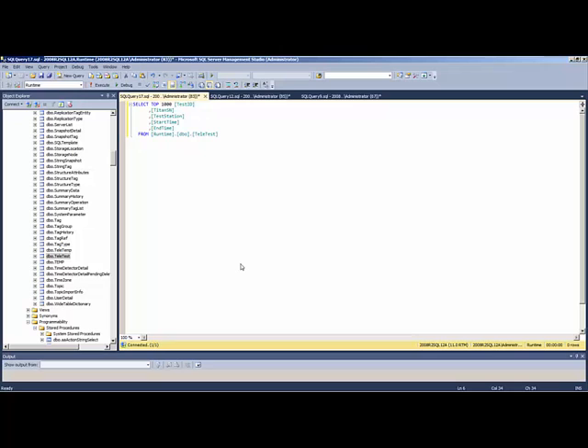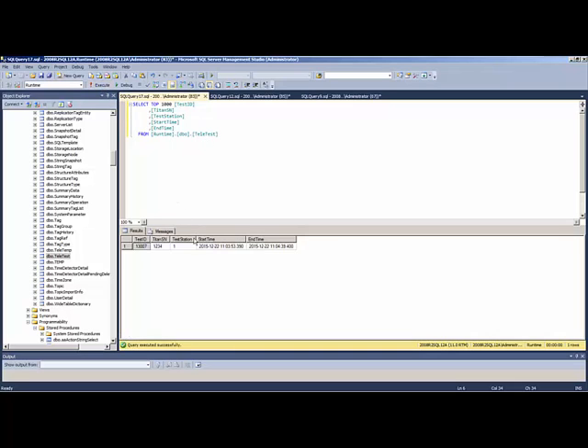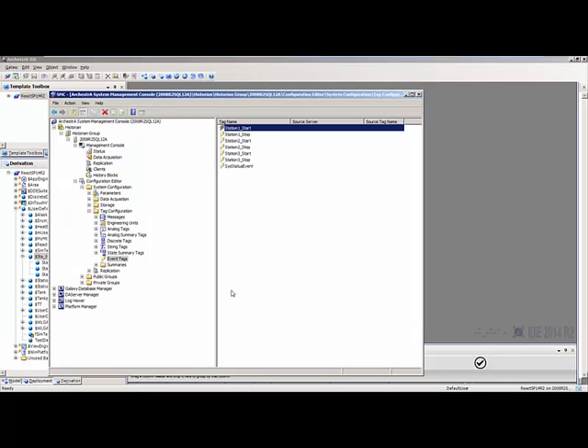Now I'm in SQL Server Management Studio. I'll do a quick select statement to look at the data that was inserted into this table about the actual test that was run. Executing the query — it's selecting all information from the table called TeleTest. You can see it has the test ID, the serial number we typed in on the InTouch screen, the test station, the start time, and the end time of the test. We can then use that start and end time to extract information from the Wonderware Historian.